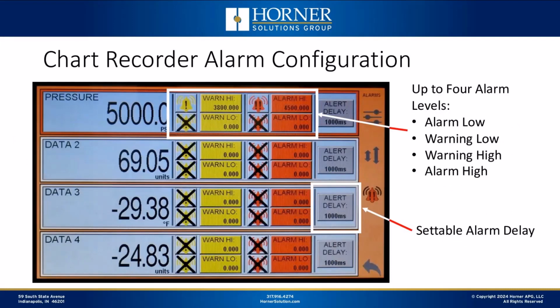And then you have alarm capability if you want to take advantage of that. So for each of the 4 channels, you have up to 4 alarm levels that you can configure. You've got alarm low and alarm high, and then you've got a warning low and a warning high. And if you really only care about one particular warning level or one particular alarm level, you don't have to configure all 4. You can configure as many or as few as you want. And then in addition to setting up the levels for each of the, up to 4 alarm points, you can also configure a delay.